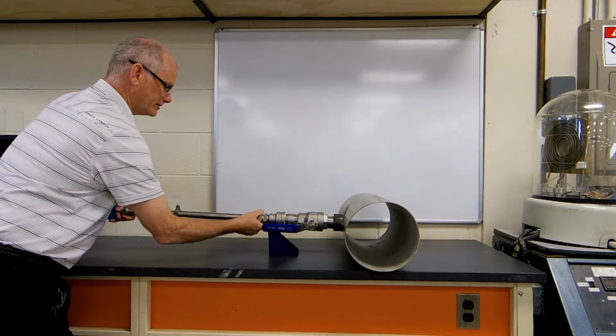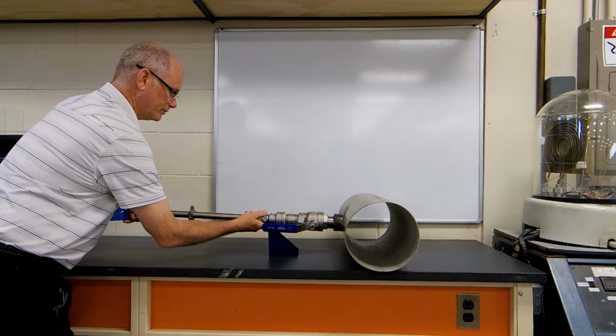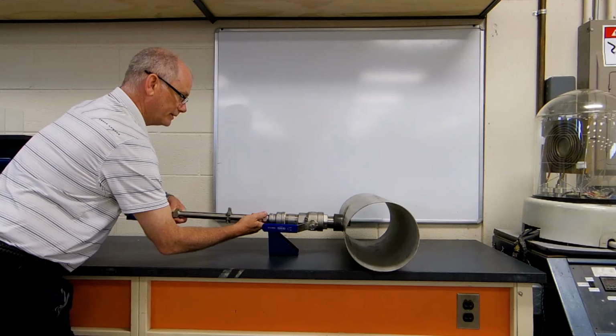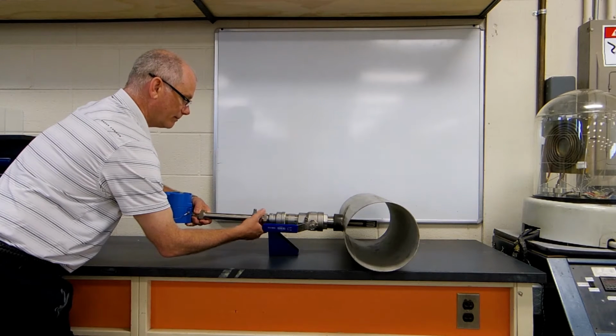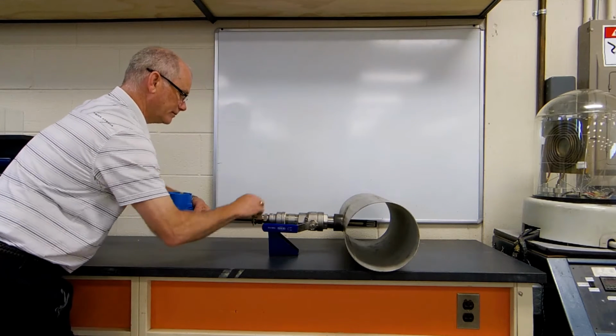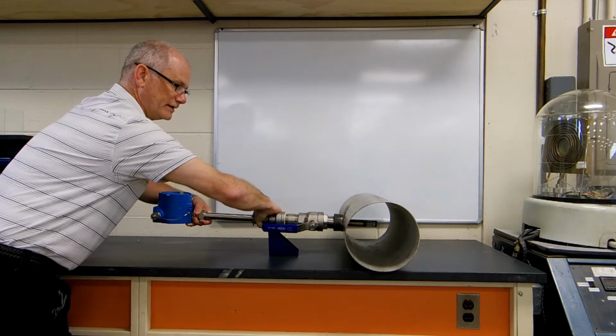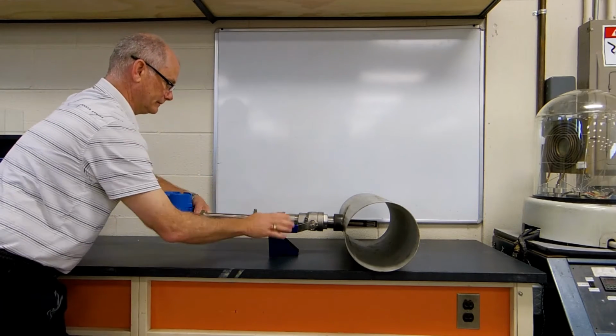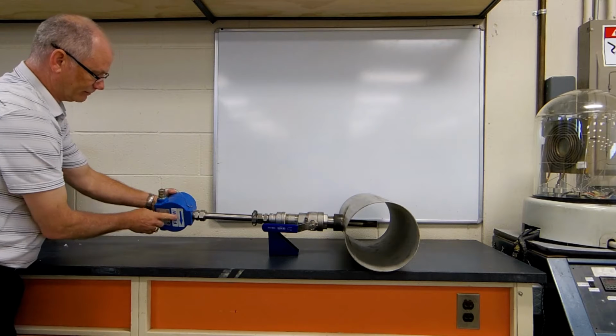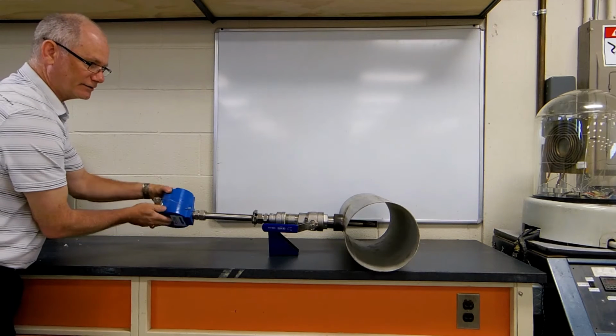Loosen the compression fitting and allow the vacuum to slowly draw the probe into the vent line to the stop clamp. Secure the compression fitting finger tight plus 1/4 turn, making sure that the flow arrow is aligned in the direction of flow.